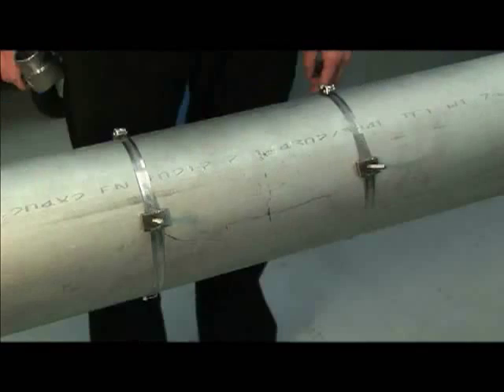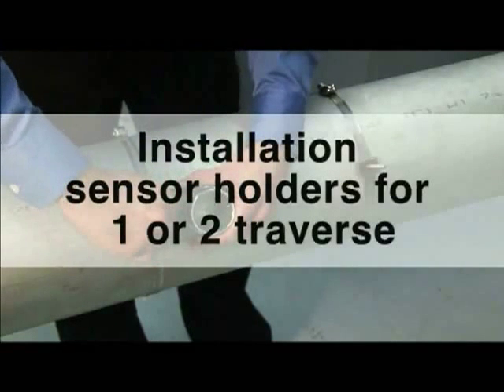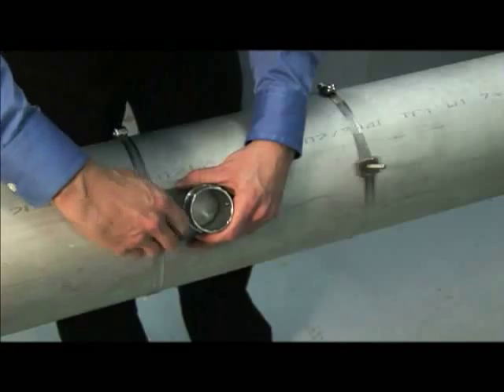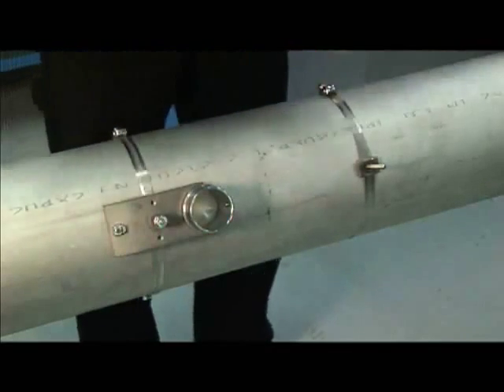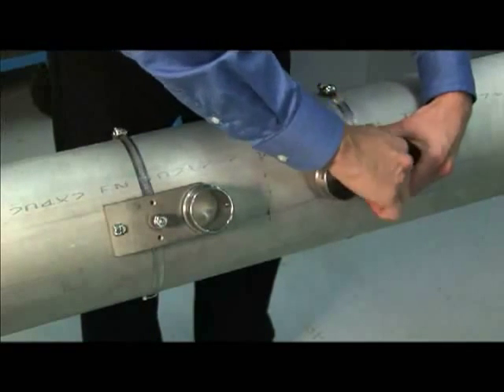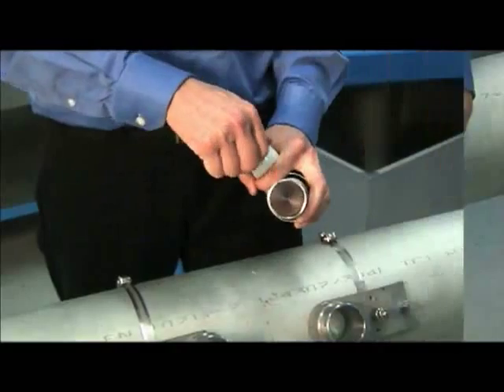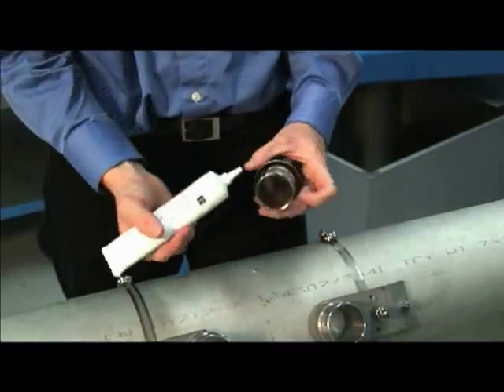The next steps are identical for both one and two traverse installation. Secure the sensor holders to the mounting post. Make sure they are facing in the correct direction as shown. After the sensor holders are fastened to the pipe, apply coupling gel to the face of the sensor. Approximately 1 mm thickness is required for the surface area which will be in contact with the pipe.